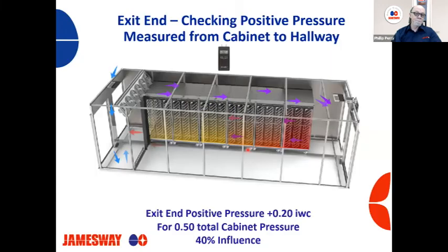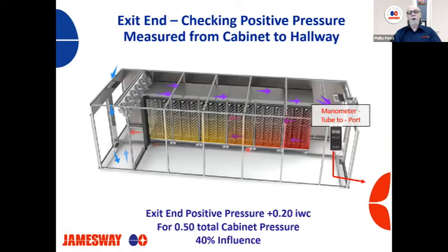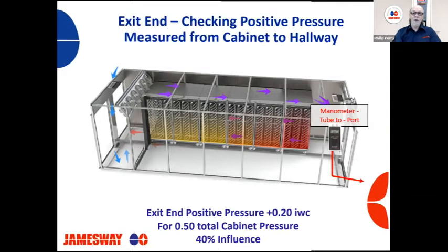And then doing the same thing, we're going to stand in our exit end, put the tube out. A lot of times, and I know I have done a lot of training where we stepped out and measured from the exit in, but really that value is probably not necessary, because a lot of times you're measuring into a hatch room that may have activity going on. And so I like, if I get my total pressure reading here and my entrance in pressure here, that's really the only two values I need, because the exit end value will add up to our entrance end value.